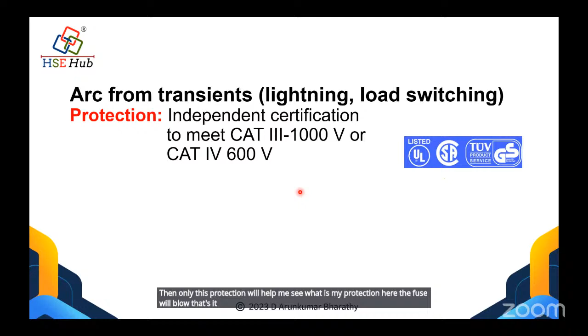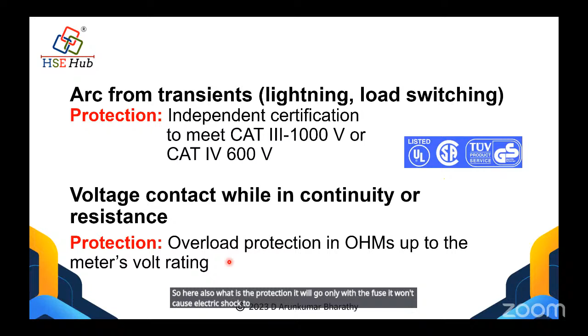Again, there is another protection also. In case I wrongly select the probe or wrongly choose the jack, for example voltage contact when in continuity or resistance, there is overload protection. Again, this will also be there in the rated instrument when we use it in the proper category. So here also, what is the protection? It will go only with the fuse. It won't cause electric shock to the user. So that is why always choose a certified and rated equipment.